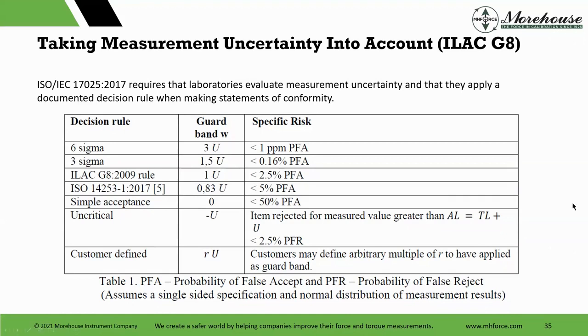So what that is, and I hope people know what that is. When we talk about simple acceptance, that just means you send a device to a calibration laboratory and they make a decision based on the specification limit. They do not take measurement uncertainty into account at all. Here's that 0. And when they do that, you could have up to a 50% risk. Because if your specification is plus or minus 5 pounds, and the lab that's making the measurement says your measured value reads plus 5 exactly, there will be 50% risk that you absorb. And we'll talk about that.